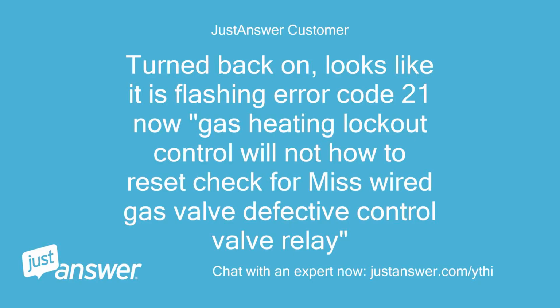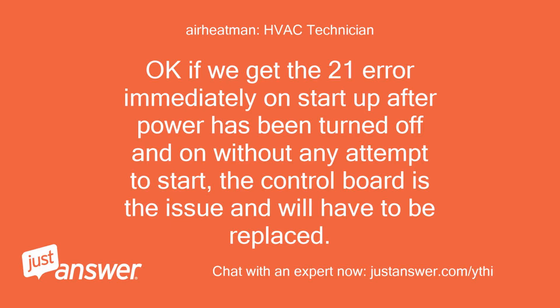Turn back on. Looks like it is flashing error code 21 now. Gas heating lockout control will not reset. Check for miswired gas valve, defective control valve relay. Okay, if we get the 21 error immediately on startup after power has been turned off and on without any attempt to start, the control board is the issue and will have to be replaced.